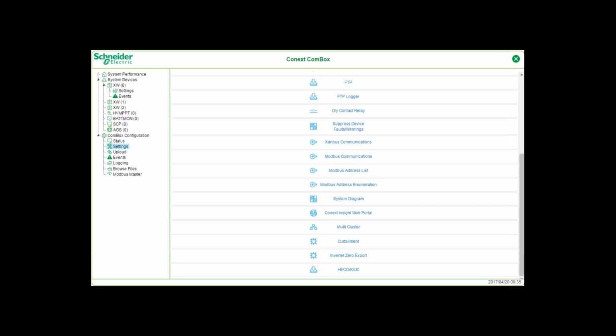Also included in the ComBox settings is the ability to suppress faults and warnings for a particular device. Say you have an external device that's starting your generator from time to time, but it's not through the AGS. You're going to get a warning that says the generator started, but not through the AGS. So things like that, if they become a nuisance, then you can just go ahead and suppress that particular fault or warning.